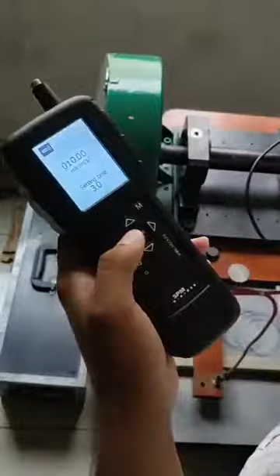Coming to the next screen, this is the sensitivity screen. We have to set the sensitivity according to the sensor. For an external sensor, you have to enter its sensitivity as written on it, and the inbuilt sensor is already tuned to 10 millivolts per meter per second squared.